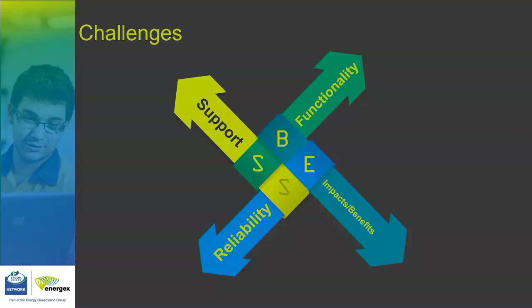We don't want the systems to all charge or discharge. How do we get diversity? If we're starting to put out all these products that are identical, that's a common mode failure. They've all got the same firmware, and they potentially all have the same firmware bugs in them. How do we manage that from the point of view of control of the network?